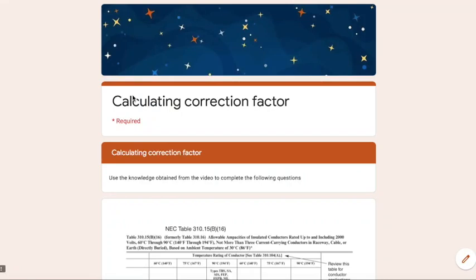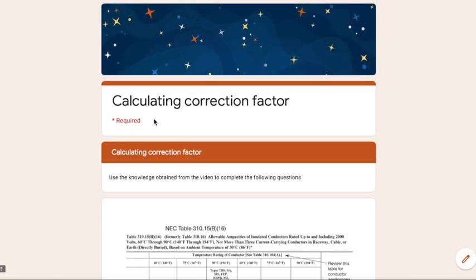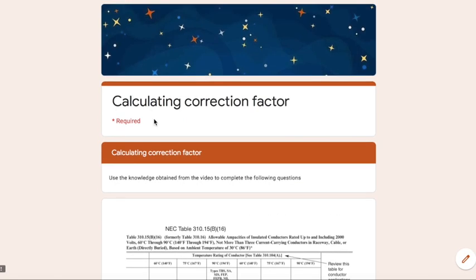Now we're going to start discussing calculating correction factor. Remember, we just talked about adjustment factor, which is the number of conductors in the conduit because of the heat they create. Well, now we're going to do correction factor, which is actually taking into account the ambient temperature in the air around the conduit or the cable.